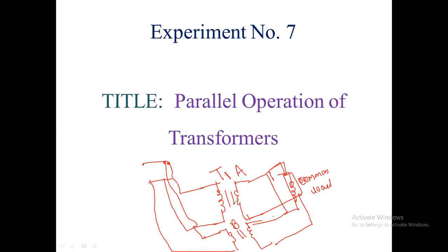So while operating a transformer in parallel, meaning connecting the primary of both transformers to a common supply voltage and the secondary of both transformers to a common load, the transformers will share that load.